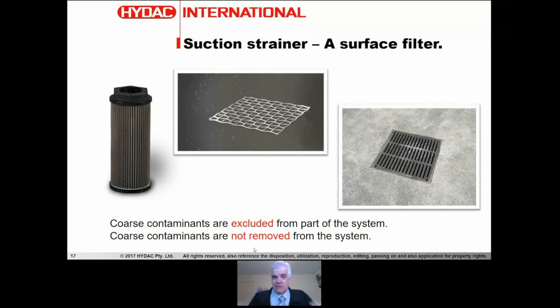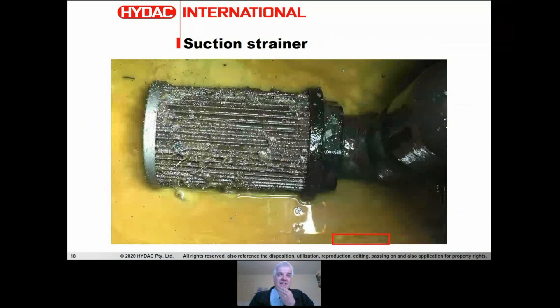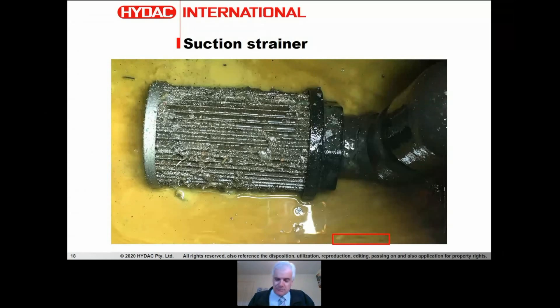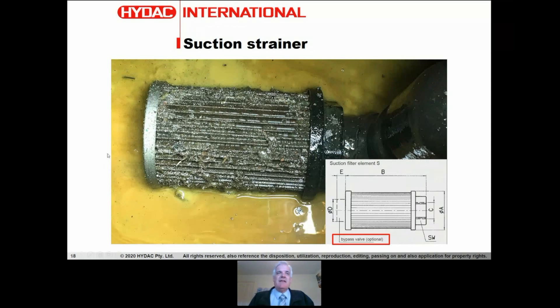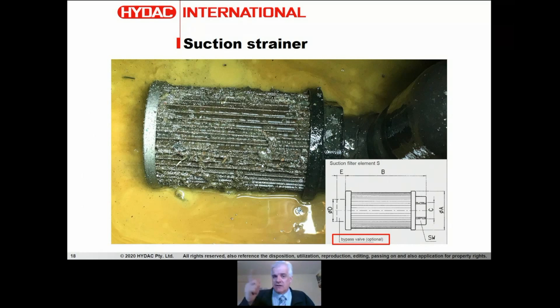Coarse filtration isn't going to clean our fluid to a level needed to safely and reliably operate the system, but it will protect the pump. Here's a photo from someone who came in for training - some systems just plainly need suction strainers. The danger is that if you have a filthy system, these can clog up. Even with large particles, they can still clog in a very dirty system, which will then cause cavitation. You put the strainer in to protect the pump, but if you're not maintaining a clean system, you're actually giving it a reason to fail.